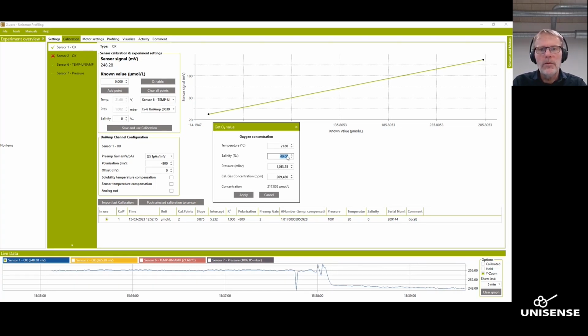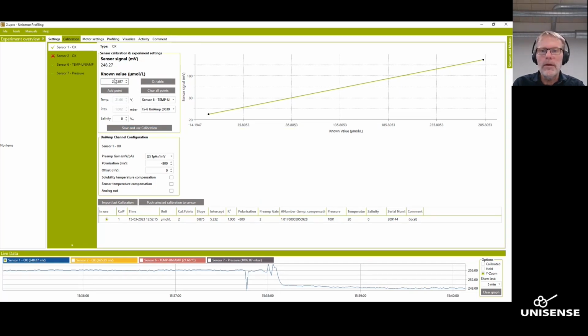It's from the Bay of Aarhus, yeah, oops, like this. The pressure of the atmosphere today is 1002 millibars, which you can see down here. So I'll just enter that. And the concentration of my calibration gas that I'm using is standard air, so that's 20.946%, or here it is written in ppm, and that gives a concentration of 237.8 micromoles per liter. I'll click apply, and it's transferred to this window here.